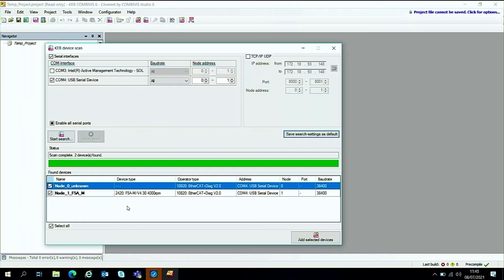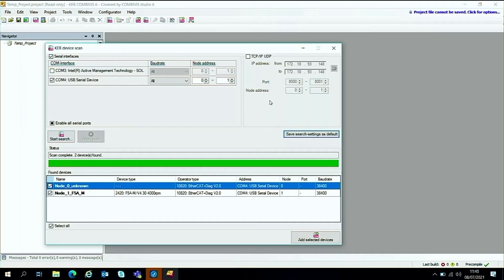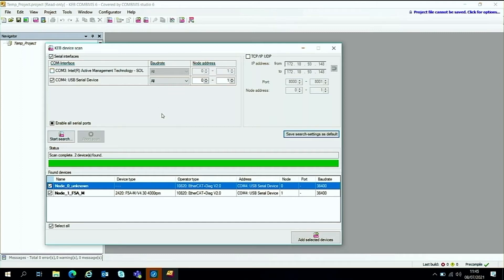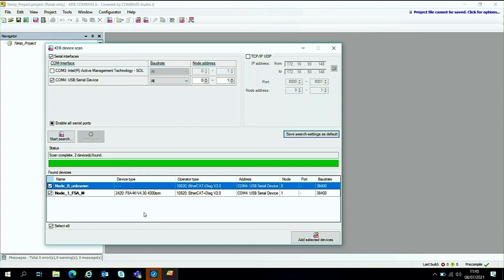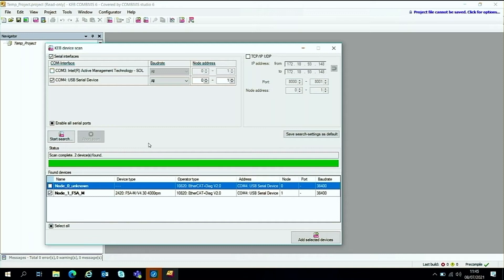One of the things to point out at this point is that we've been scanning node addresses 0 and 1 on all the baud rates using the serial port, this COM port 4. One of the features of this software is that it will always report as many drives as you have scanned for. So you've got to bear this in mind.